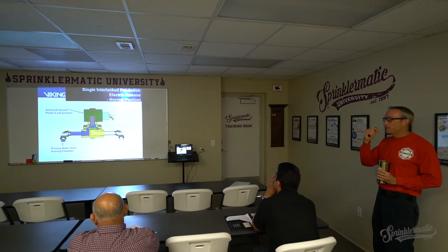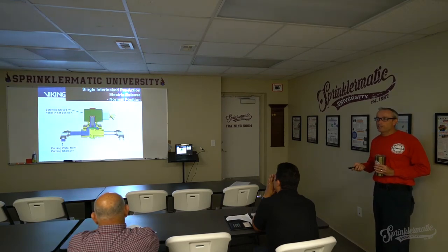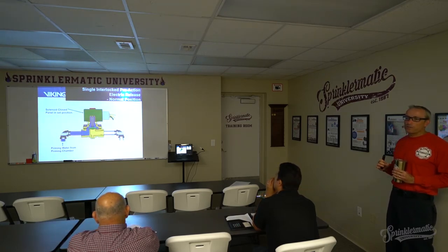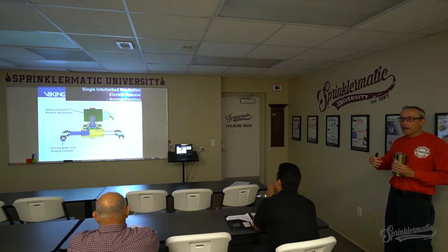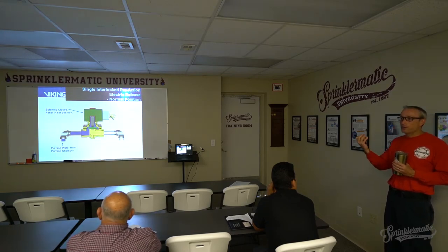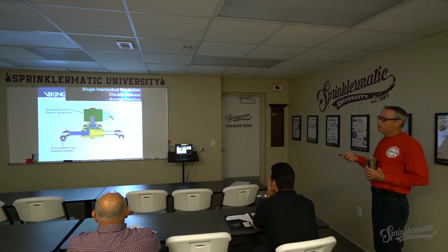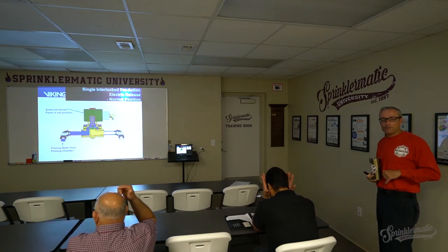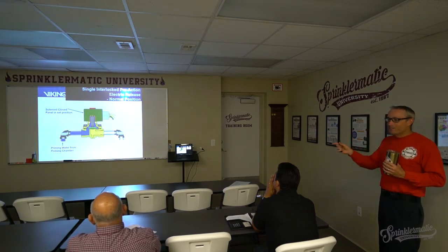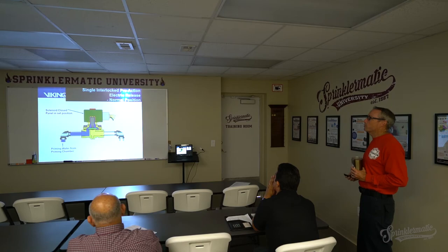One of the things I learned from one of the guys from Viking that was here, when talking about the panels, is that a lot of people have problems resetting the panels, and they call and ask for troubleshooting. He says a lot of the times when they say, we can't get your panel to clear out, we can't get a green panel here, he asks them, are your solenoid valves installed correctly? Because if they're installed backwards, in and out versus out and in, then the system isn't going to work right. So a lot of times when installing them, they call Viking and say, hey, we're having a hard time setting up your system here, and they'll say, check your solenoid valves. You don't think that it matters, but it does matter. Every valve has an in and out, and it has to be put on the trim the correct way.